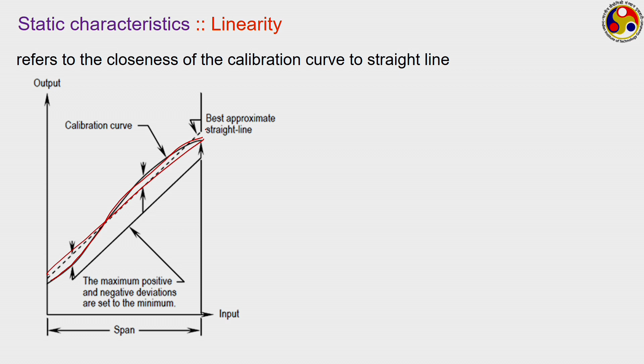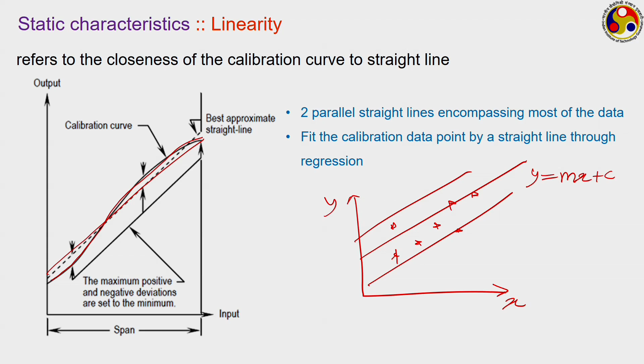There are two ways we can do it. One is to put two parallel straight lines, like let me say an example. Let us say this is your input x, this is your output y, and these are a few data points that we have got during the calibration. Now, one option is we can put two straight lines which encompass at least most of the data and try to get a measure from there. The other is we try to find a calibration straight line using a relation y equal to mx plus c, identifying the values of m and c from this calibration curve, and use it for unknown measurement.